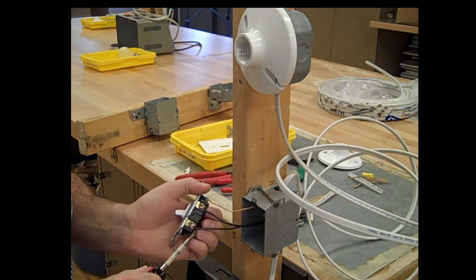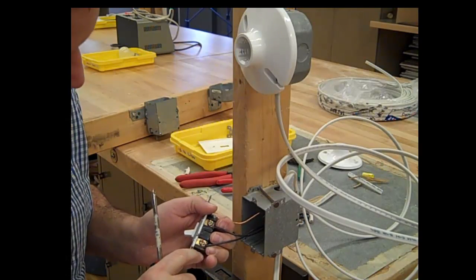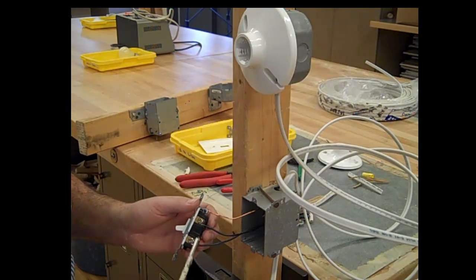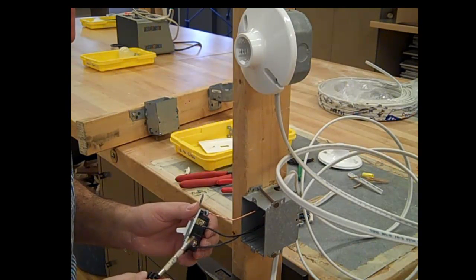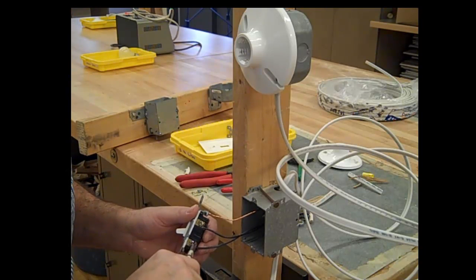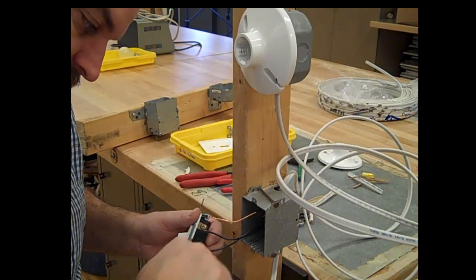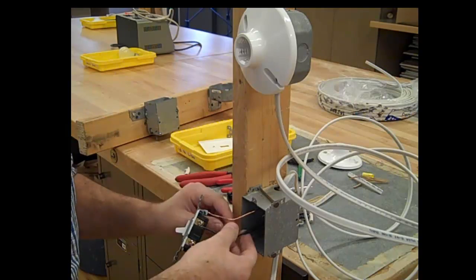Notice the direction that the hooks go around these screws. That is important. The hooks go around the screw in the clockwise direction. The reason is if you did it backwards, when you go to tighten this up it actually kicks the wire off. If you do it in the clockwise direction, when you're tightening that screw it's sucking the wire back in.